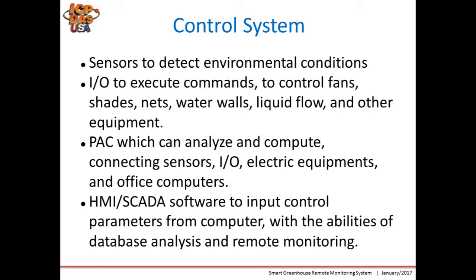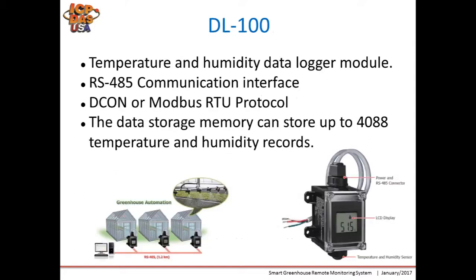A control system requires sensors to detect environmental conditions such as temperature and humidity inside and outside the greenhouse, as well as sunshine, wind direction, and speed. Second, we need I/O to execute commands to control fans, shade nets, water walls, liquid flow, and other equipment. We also need a controller to connect those sensors, I/O, electrical equipment, and computers. Lastly, we need HMI or SCADA software to input control parameters from a computer, with the ability for database management, analysis, and remote monitoring.